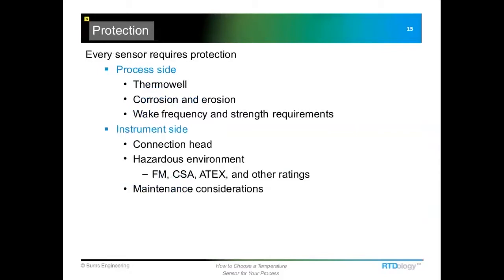The next section, we're going to talk about how to protect this sensor. We've got protection on the inside with a thermowell, and we've got protection that's required on the instrument side, or the outside of the process. Inside, we've just talked about the thermowell, and we have to look at corrosion and erosion of the thermowell. The most important part of this would be the wake frequency and strength requirements. We'll get into more detail as we go along. The wake frequency and strength calculations are very important when a thermowell is used in a flow that's going fast enough to cause some vibration of the well.